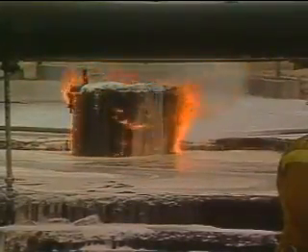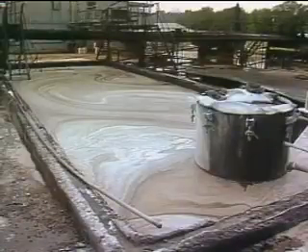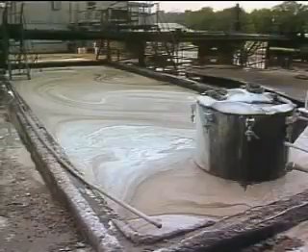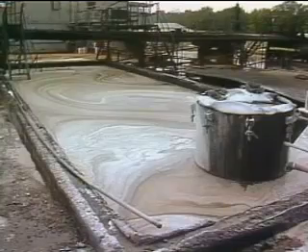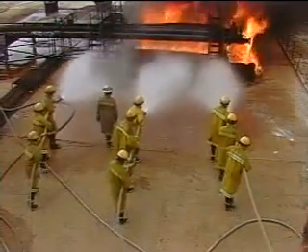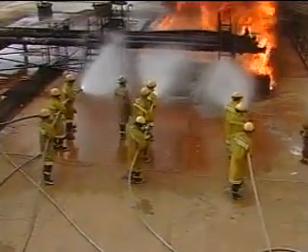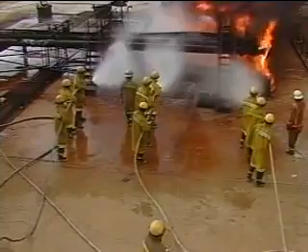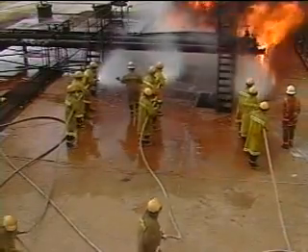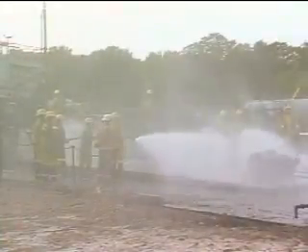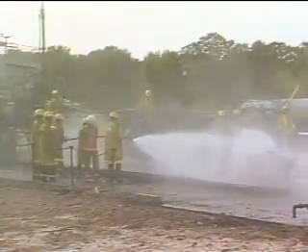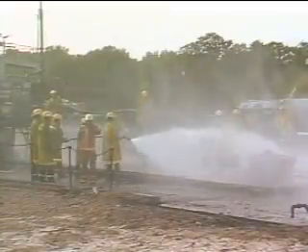Once enough foam is applied, it'll form a protective blanket and stop the fire. And remember, water tends to destroy the foam blanket. If cooling or protection of other areas is necessary, use a fog pattern or attempt to knock down the fire and do structural cooling with straight or broken streams before foam is applied. If cooling is required after foam is applied, use a fog pattern and be careful not to disturb the foam blanket.